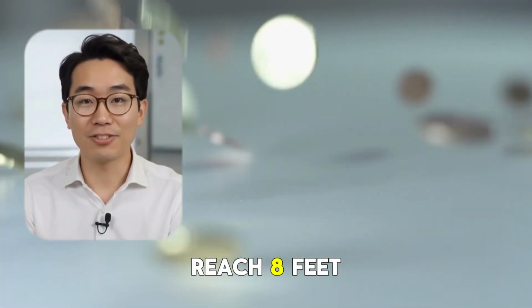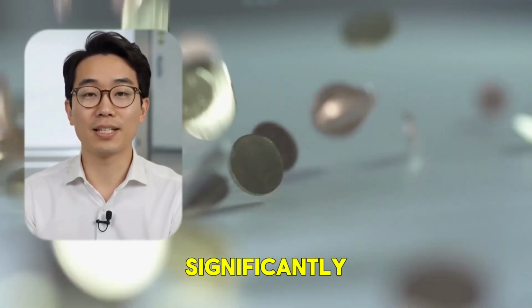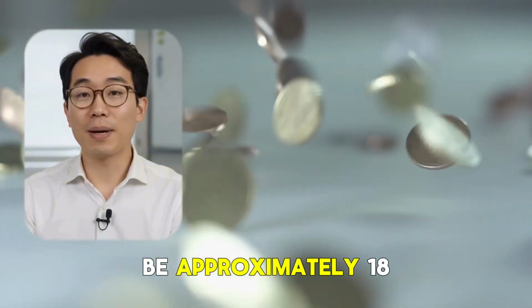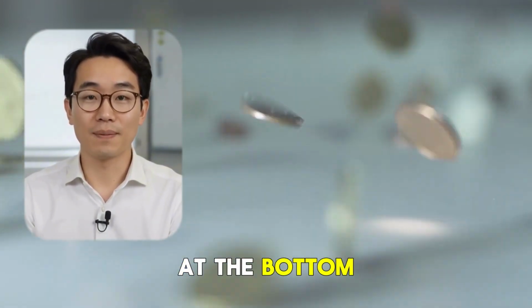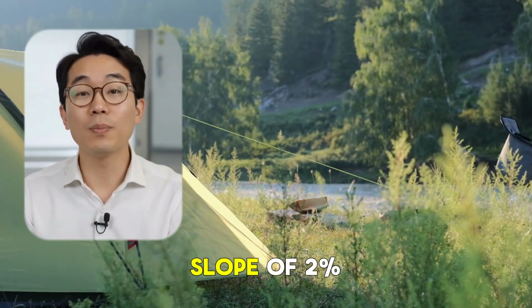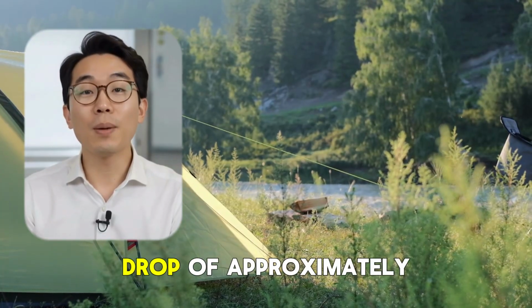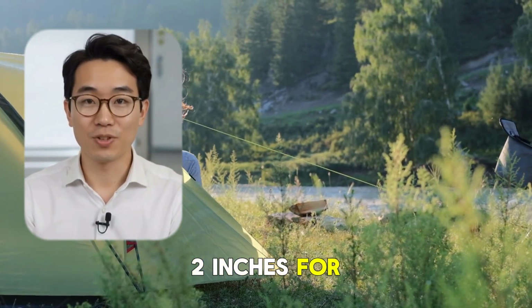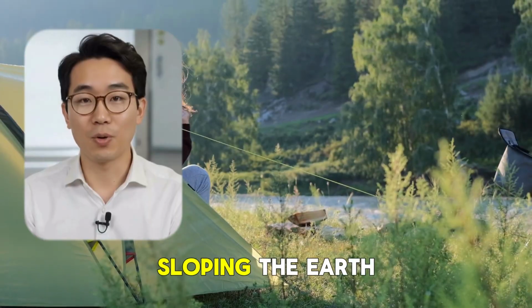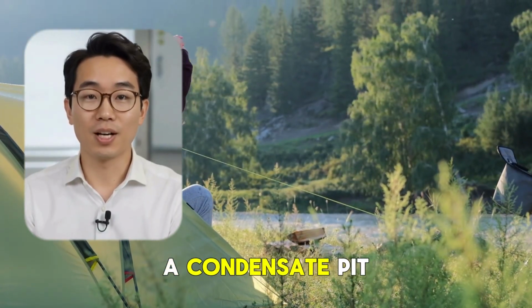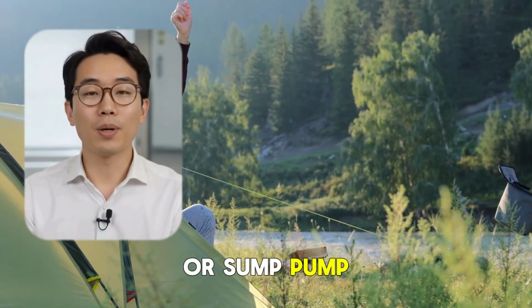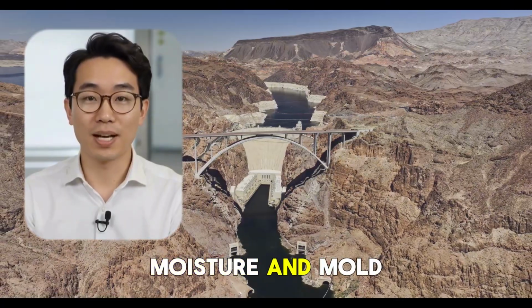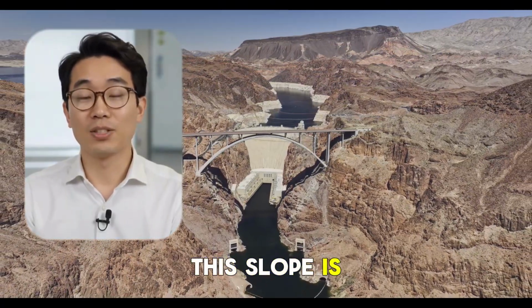If you can reach 8 feet, the performance improves significantly. The trench should be approximately 18 inches wide at the bottom. Lay the pipe with a consistent slope of 2%, which means a drop of approximately 2 inches for every 8 feet of run. Sloping the earth tube 2% towards a condensate pit or sump pump prevents buildup of moisture and mold growth. This slope is critical.